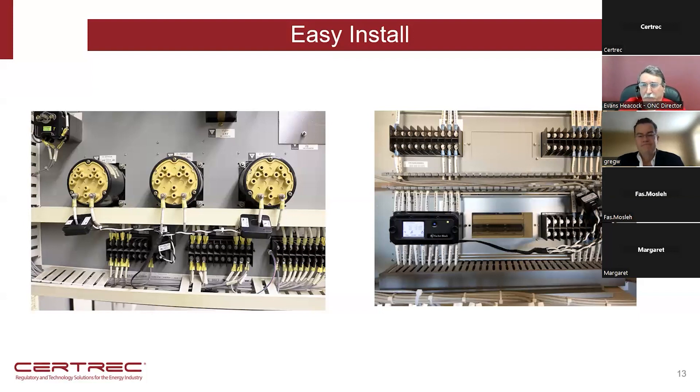From a communication standpoint, our devices have two native modes of communication. One is standard Ethernet to a router in the substation out to the customer's network — some customers even put the server right in the substation — enabling high-resolution waveform transfer. We also communicate DNP3, so many of our implementations stream waveform and high-resolution data to WaveIQ, but also stream DNP3 SCADA information to third-party SCADA systems. It's actually very simple and straightforward.